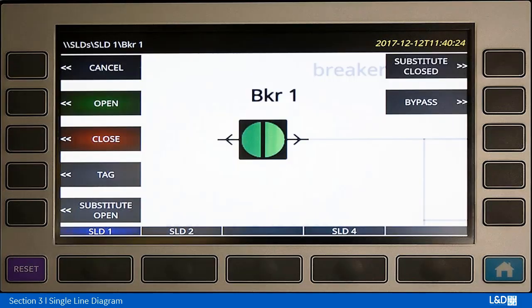If we want to go ahead and control breaker number one, we're going to select the button associated with it and we'll see this kind of screen. The choices are to either cancel the operation, open, close, or there's a tag, substitute, and bypass that we've programmed — I'll talk more about those in a moment.